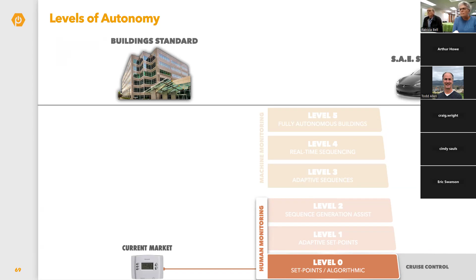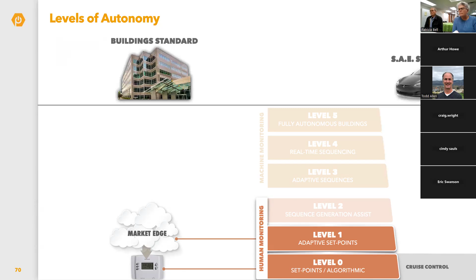Level 1 autonomy is adaptive set points, and we do this already. This is outdoor reset, supply air temperature reset, pressure resets, things like that. These are changing set points, and that's sort of the cutting edge of most currently installed buildings.